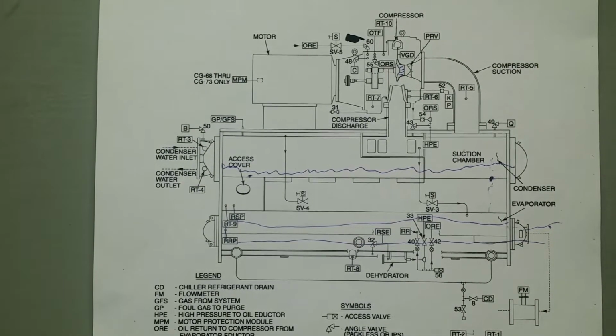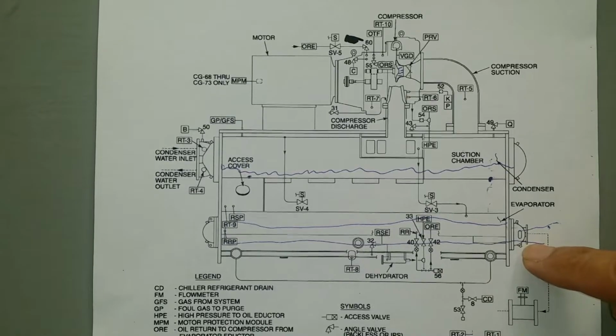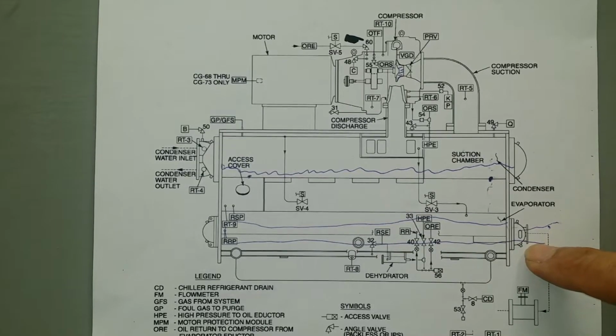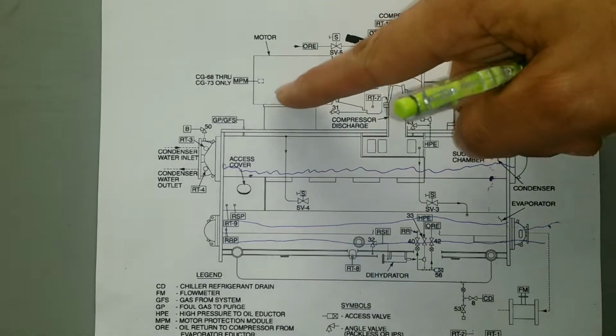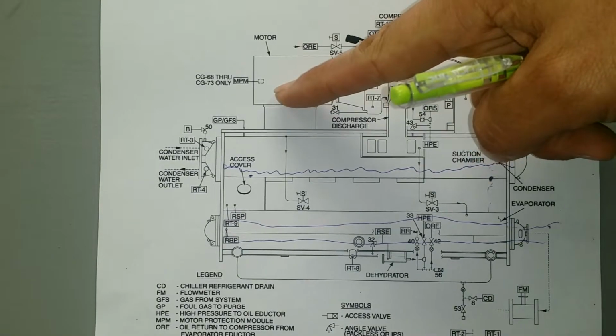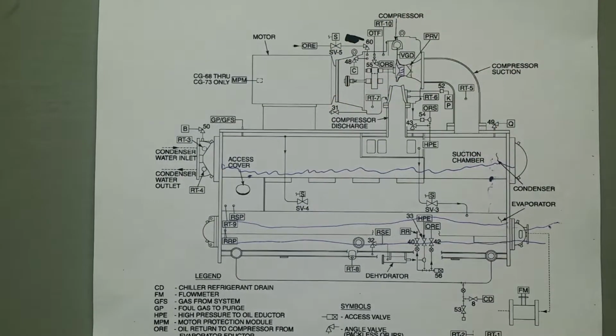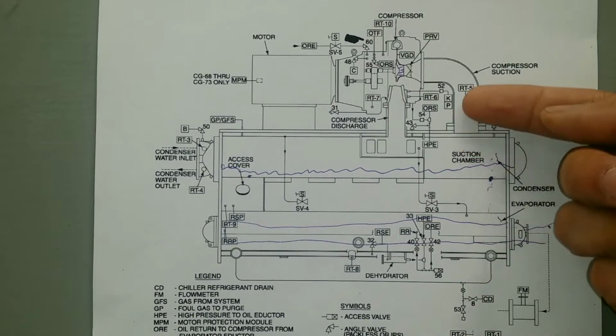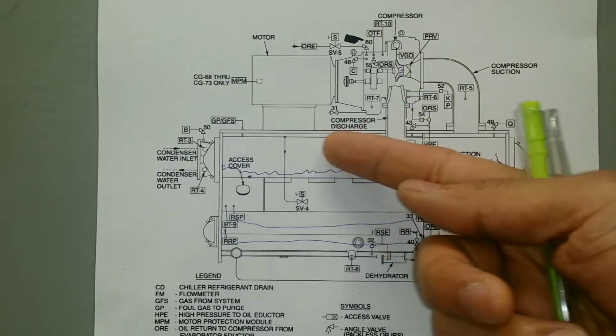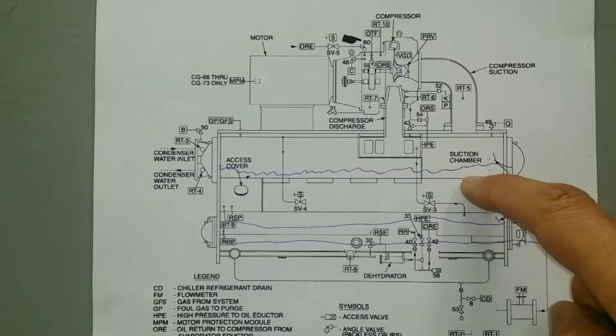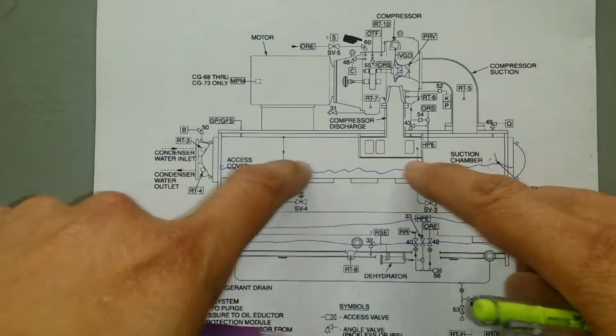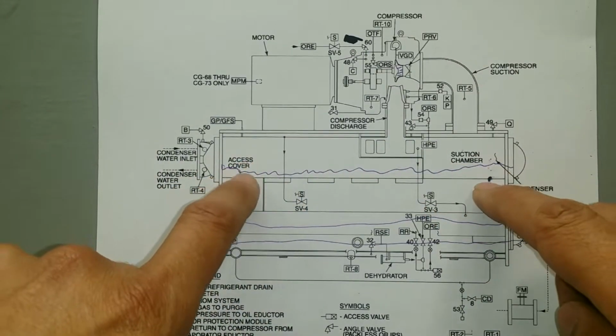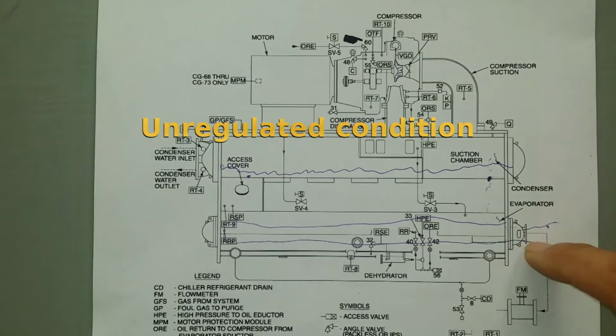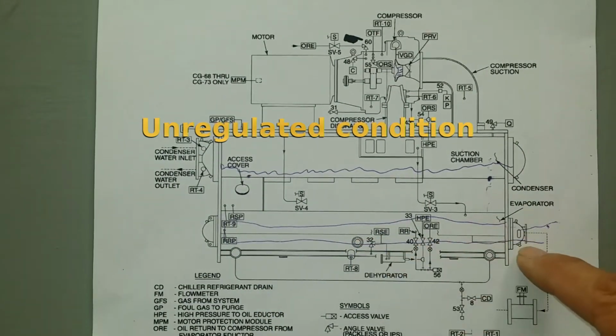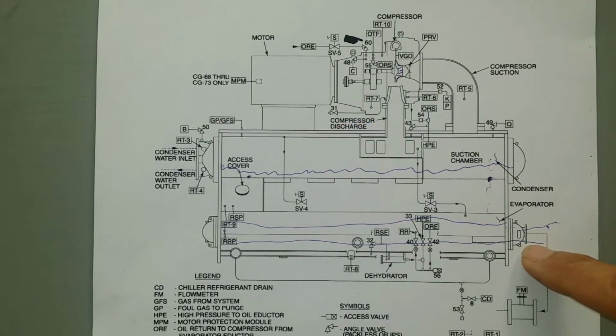Now, very important, in my system, the output of the chill water is supposed to be 44 degrees. But my motor always runs at the same speed and it's always on. So if we would just let it be, it will put all that high pressure refrigerant over here, which will be liquefied, and because of so much pressure over here, all the liquid will be pushed at a faster rate, and the pipes that contain the chill water will get so cold that the output over here will be less than 44 degrees.